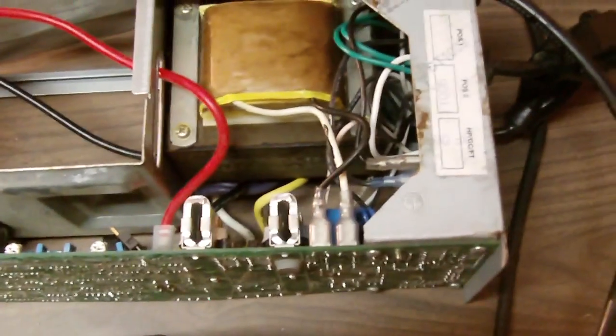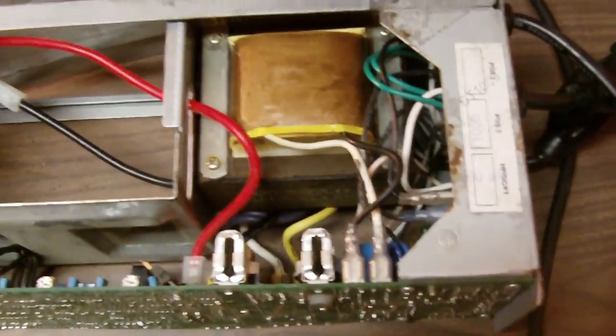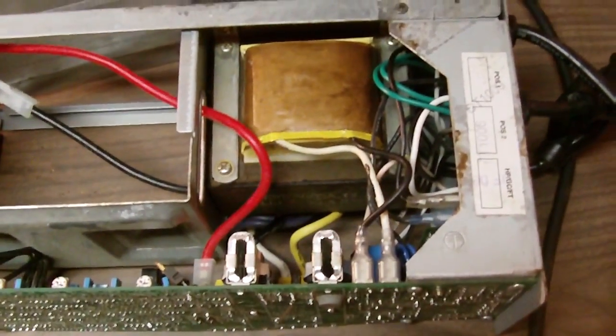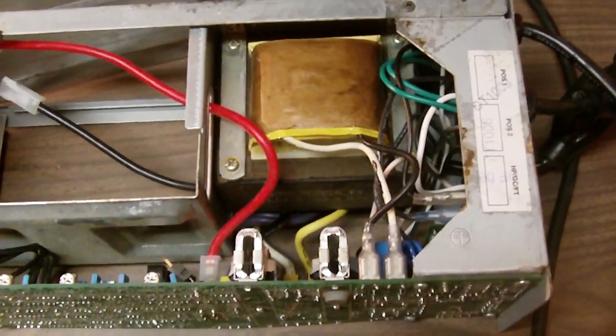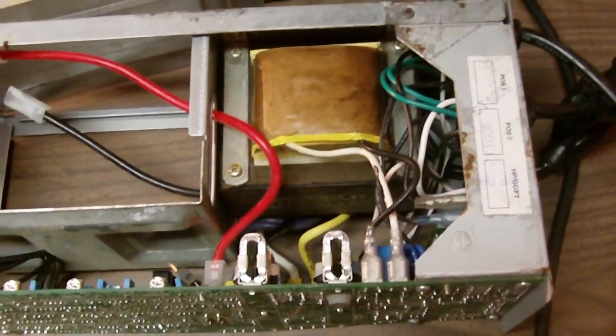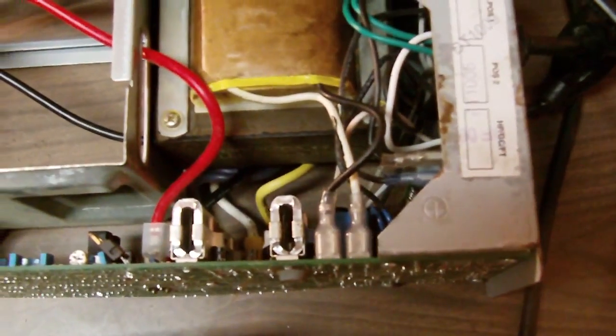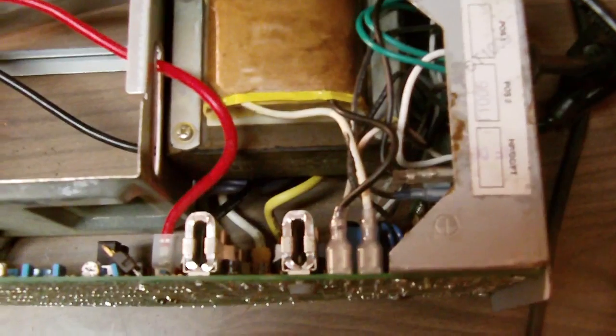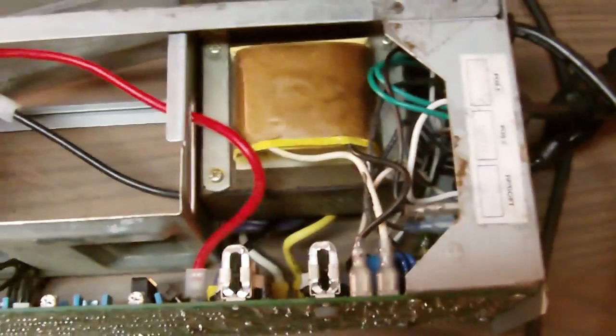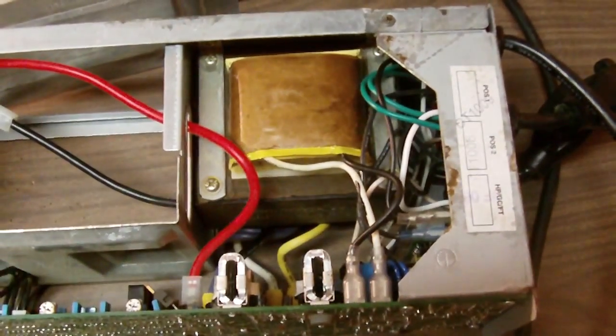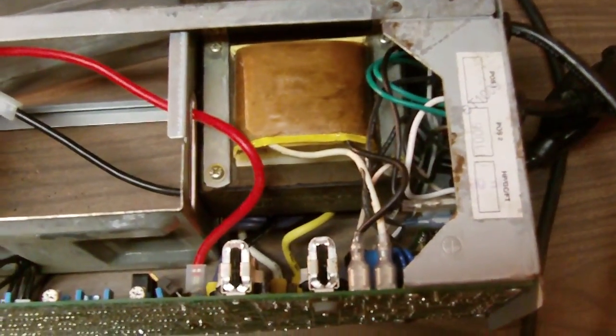So the computer, or whatever you have plugged into your backup unit, is actually running off of the inverter side. So it's always running on inverter. It doesn't just switch from 110 to inverter. And then what happens is when the power goes out, this transformer shuts down and then it switches directly over to battery, which these wires were connected to the battery.